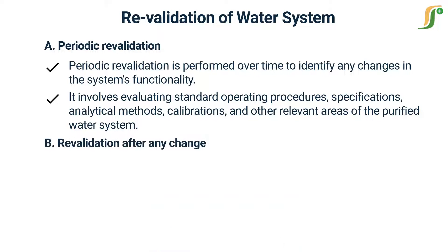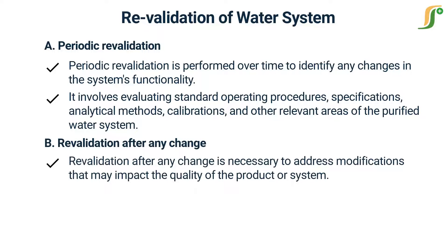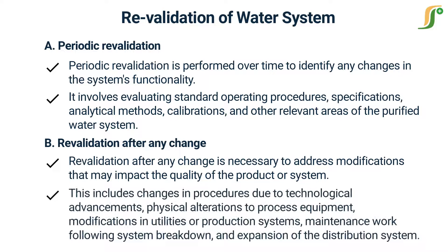Revalidation after any change is necessary to address modifications that may impact the quality of the product or system. This includes changes in procedures due to technological advancements, physical alterations to process equipment, modifications in utilities or production systems, maintenance work following system breakdown, and expansion of the distribution system.